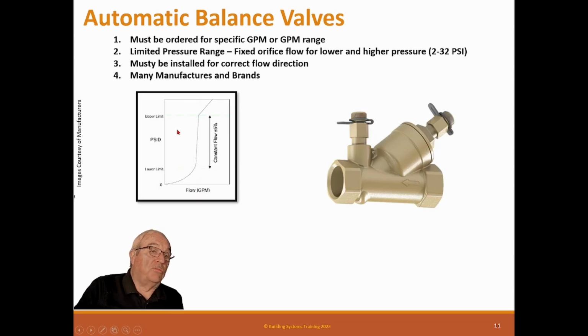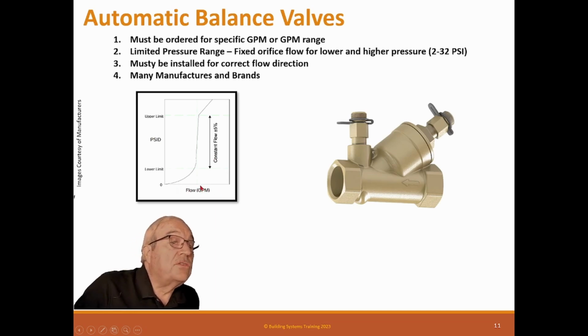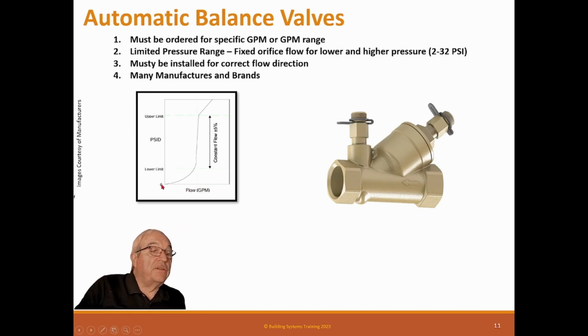And this is what a flow profile looks like. So here's your flow in GPM. If your head is down here, it's 0, and as the pressure comes up, it's going through a fixed orifice. It gets to here, the spring starts working, so it keeps the flow almost constant. And once you exceed its pressure, it takes off as an orifice again. So that's how their curve looks.